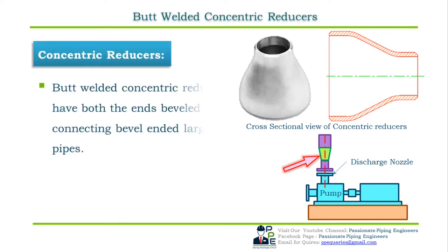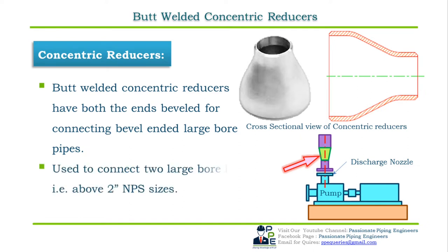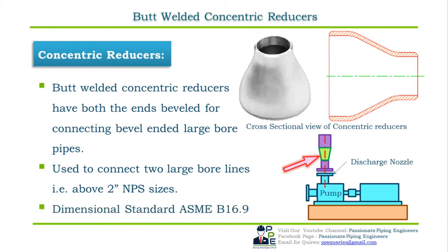Butt welded concentric reducers have both ends beveled for connecting beveled large bore pipes, as shown in the cross-sectional view. They are used to connect two large bore lines or pipes — that is, line sizes above 2-inch NPS — for example, 8-inch NPS to 6-inch or 4-inch NPS. The dimensional standard for butt welded concentric reducers is ASME B16.9.